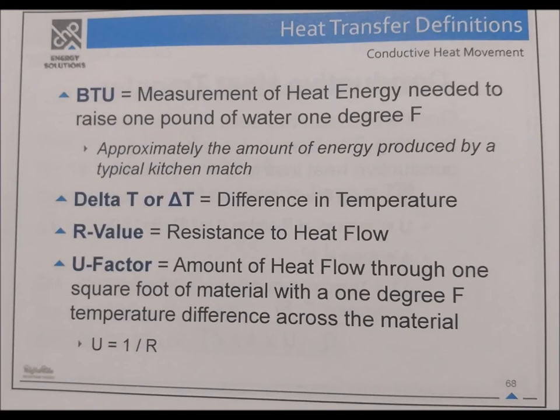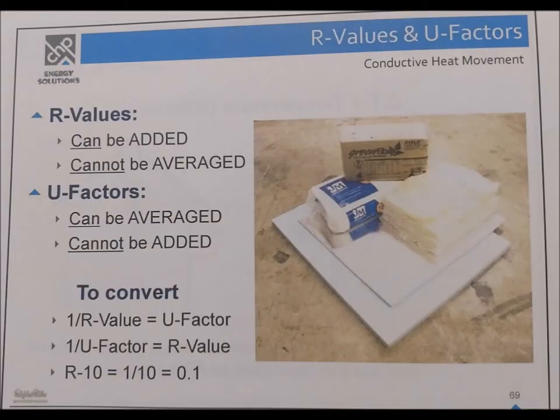R-values and U-factors: R-values can be added but cannot be averaged. U-factors can be averaged but cannot be added. To convert: 1 divided by R equals the U-factor; 1 divided by U equals the R-value. For example, R-10 gives a U-factor of 1 divided by 10 equals 0.1.